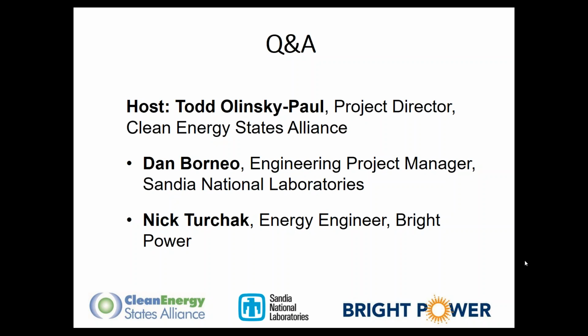So first question, and this is kind of involved, so we may have to take it a few steps at a time. The question is, for a 20 megawatt battery storage plant, can you discuss the following RFP elements: storage capacity in megawatt hours, max discharge rate at nameplate 20 megawatts, hours of discharge at max rate, max charge rate in megawatts, and output-input cycle efficiency as a percentage. All right, so that's I think 5 different things.